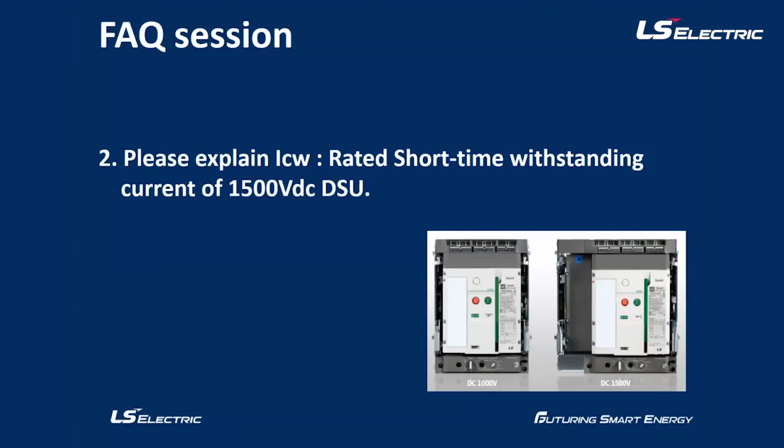So we've tested 150 kA for 50 milliseconds and 180 kA for 5 milliseconds in our laboratory, PTNT. So we already have it in our report. So I think we are proud to present that our system is well prepared.